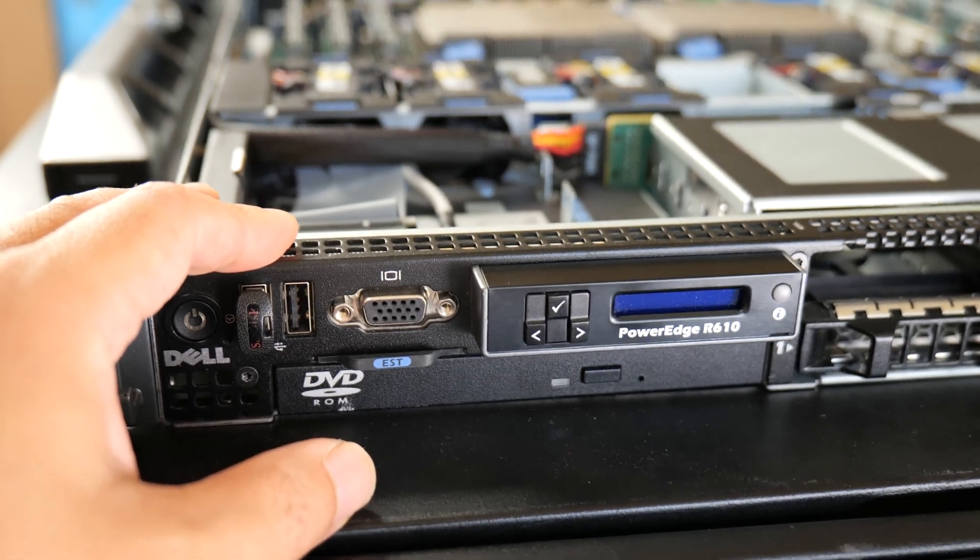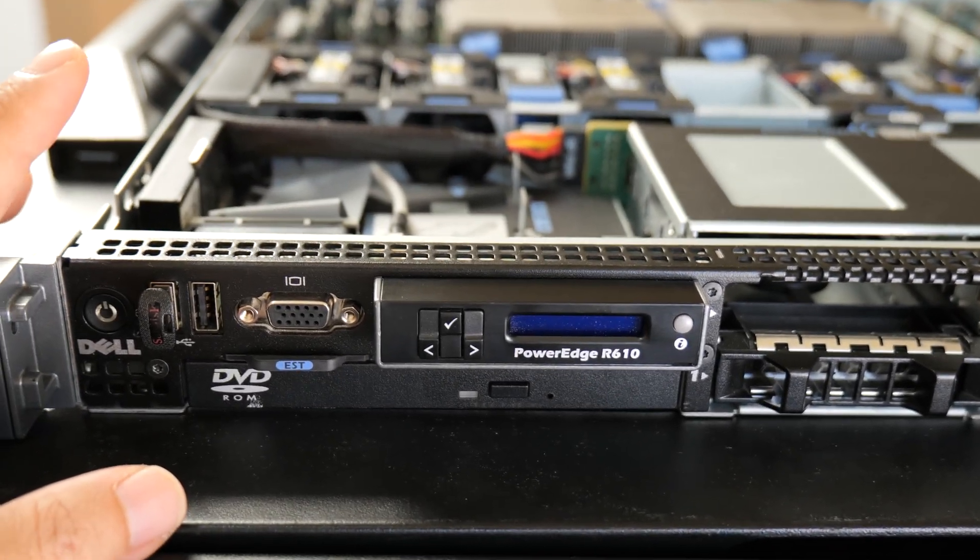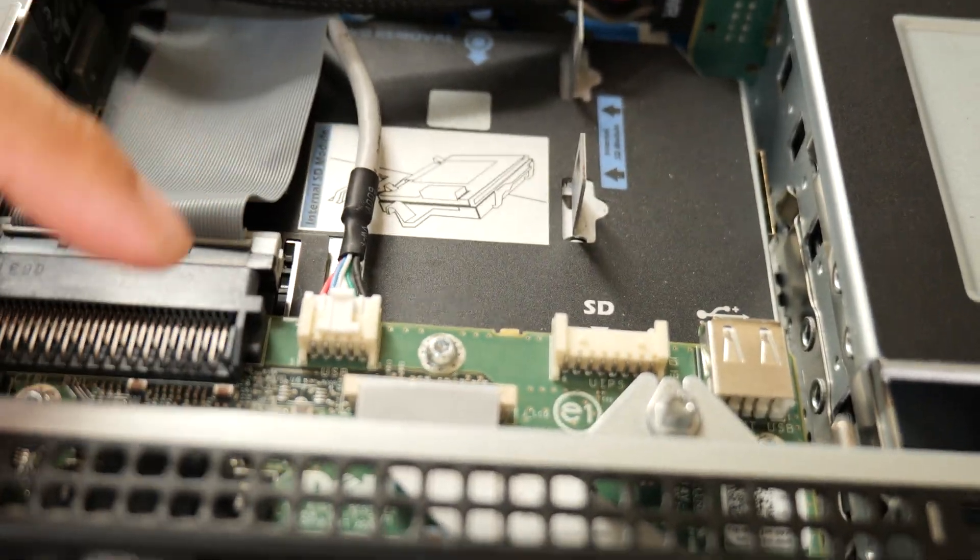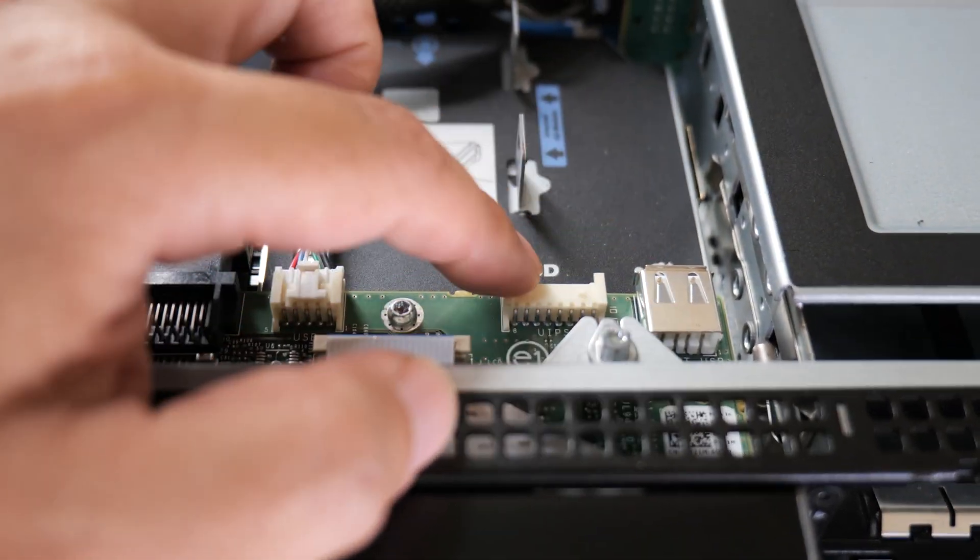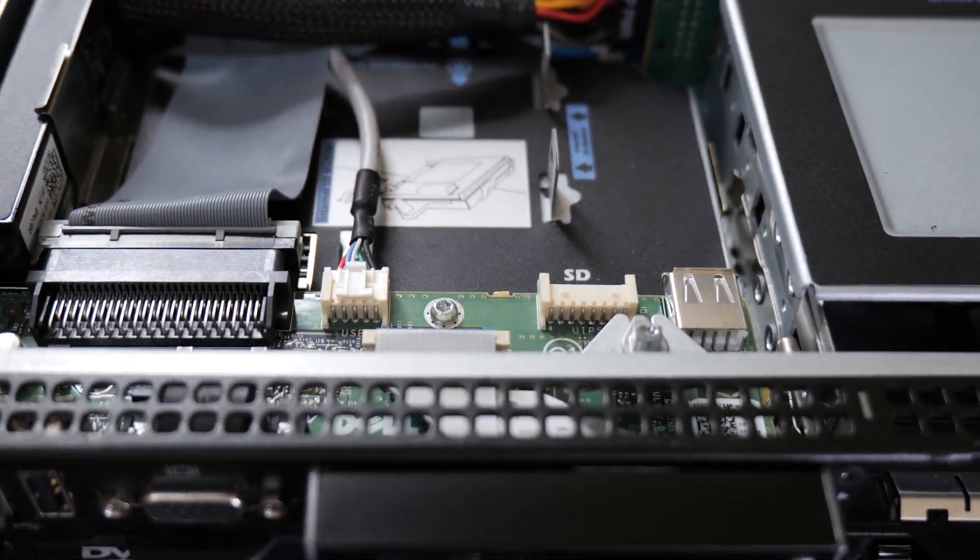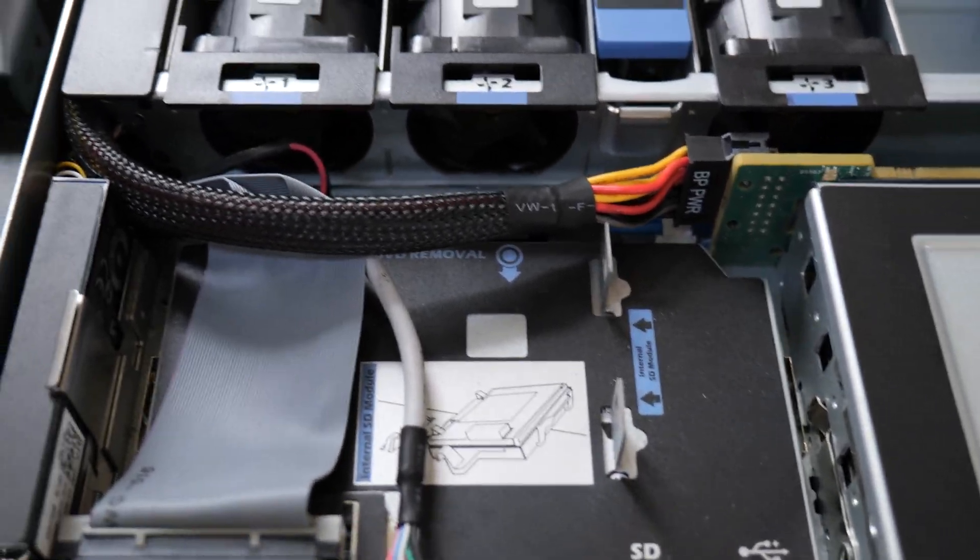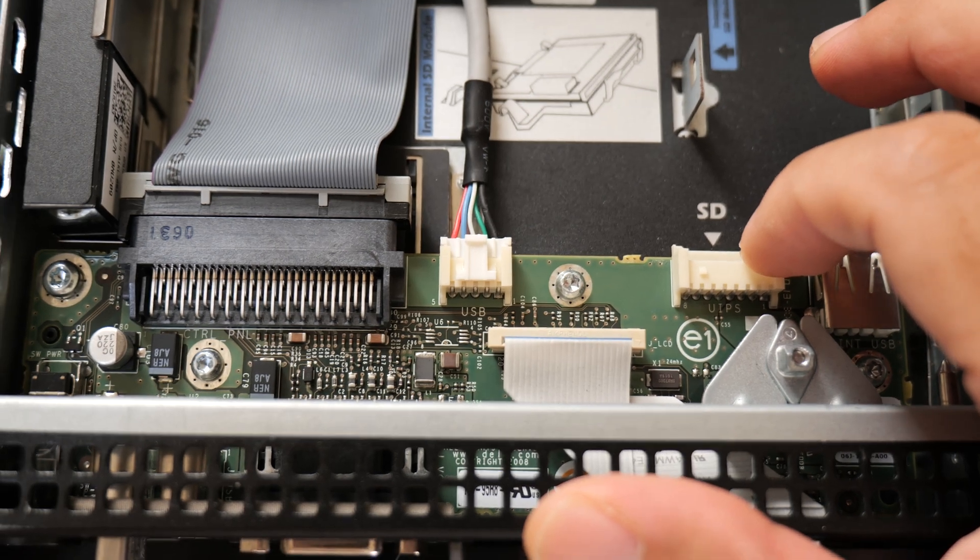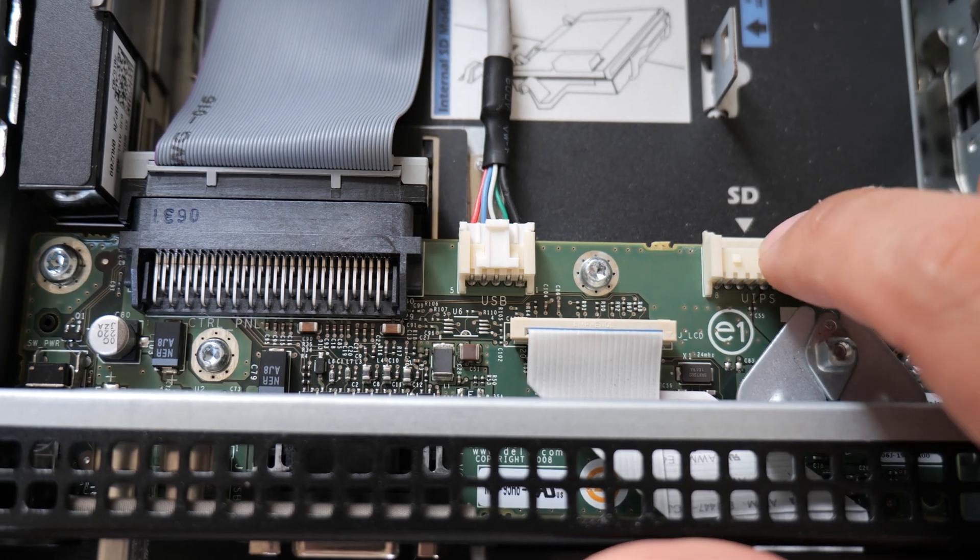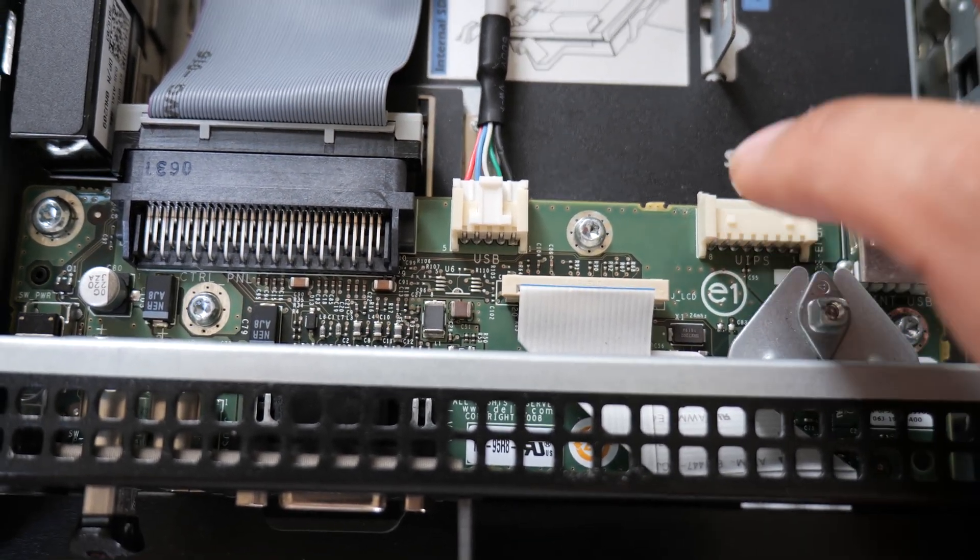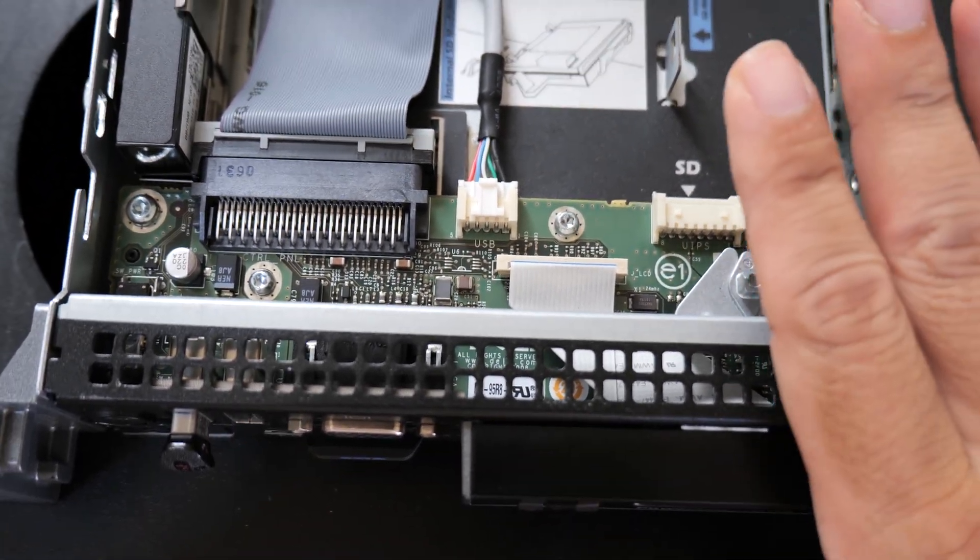All right guys, so I got the lid removed and the ambient sensor, the temperature sensor in this server is actually located on this logic board right here. That's part of the front panel IO and the internal USB and SD card controller board. This board somewhere on it is the ambient temperature sensor. And this is basically the board that you're going to want to replace if you have this problem where you have an unusually high ambient temperature sensor reading. Once you fix that and the server gets the correct temperature, then those problems with the high fan speeds are going to go away.